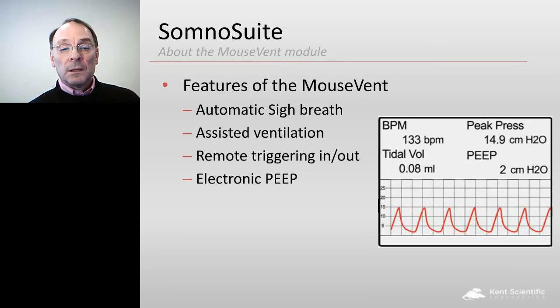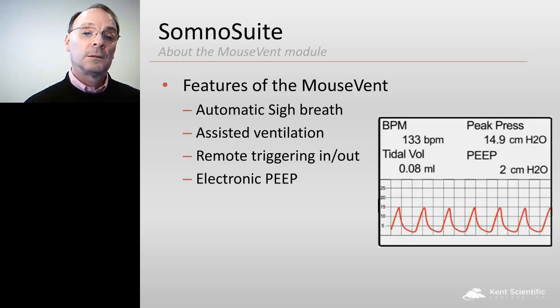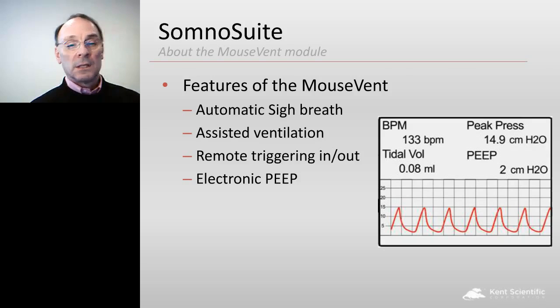Then other capabilities of the mouse vent: it has automatic sigh breath. You can dial in a sigh breath down to inserting one every 10 breaths. The sigh breath is a breath that is at a higher pressure typically. So if you're ventilating at 15, you might have a sigh breath of 20 or 25 to expand the lungs periodically. Assisted ventilation, if the animal is spontaneously breathing, you can still have them intubated and give them a breath every so often.